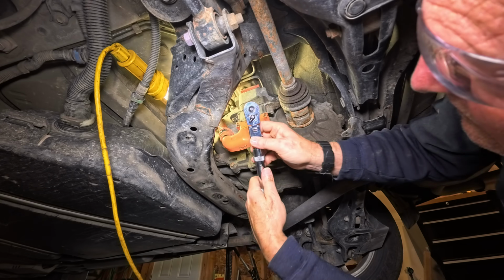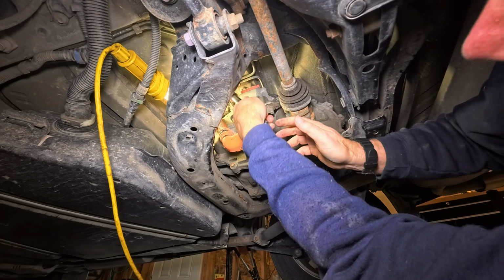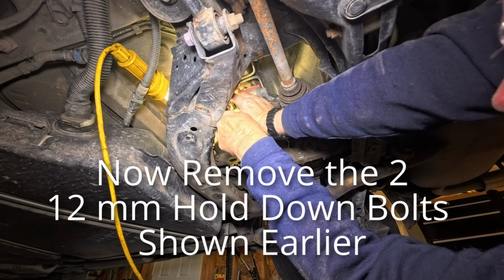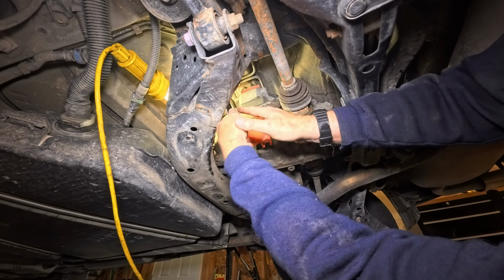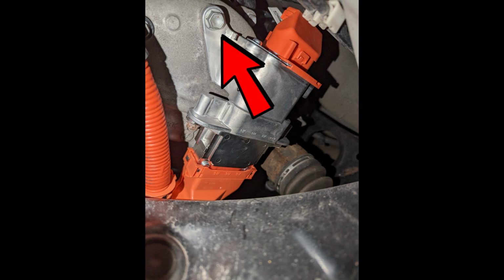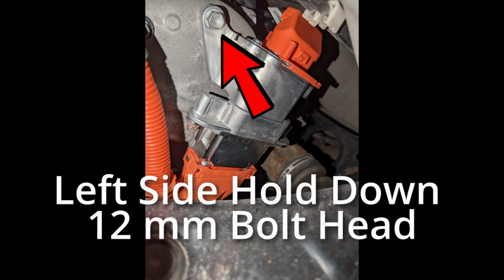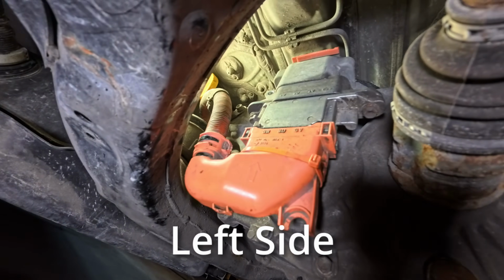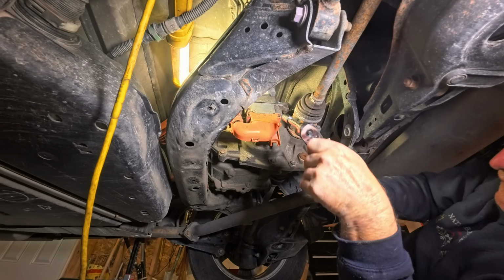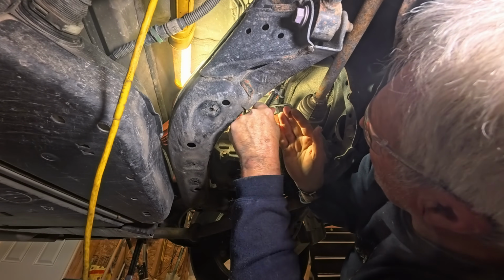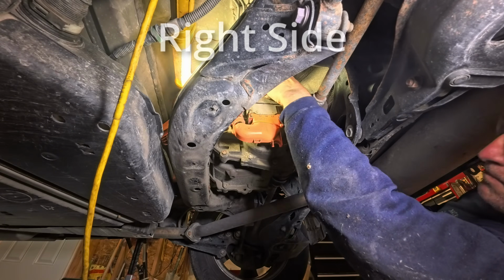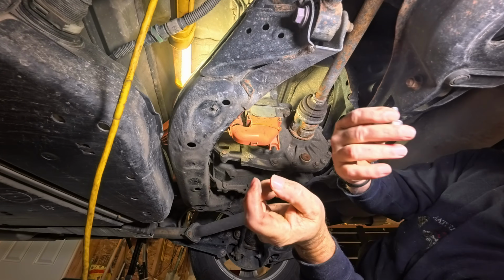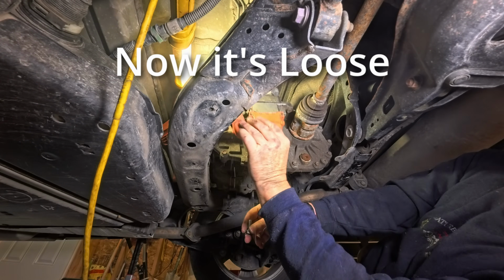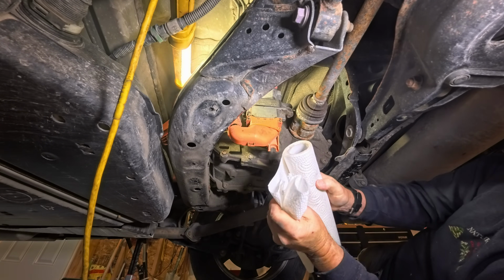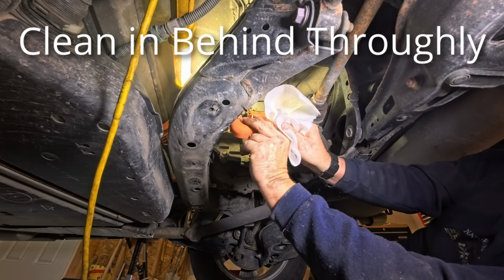Now we can remove the 2 12mm bolt heads that secure the connection to the motor in order to install the back half of the cable box. Left side is out. Now for the right side. Right side bolt is also out. The connection is now detached from the motor, and we need to thoroughly clean the back side of the connector to ensure good seal around the inlet and outlet of the new cable box, where the silicone will be sealing.